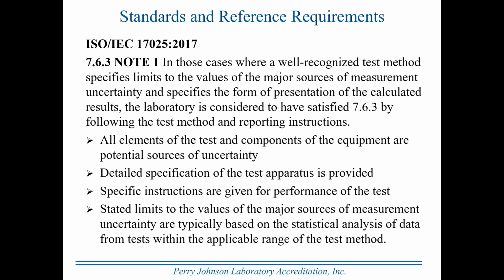Stated limits to the values of major sources or contributors of measurement uncertainty are typically based on the statistical analysis of data from tests within the applicable range of the test method. In other words, if the test method is good from some small magnitude to a large magnitude, then in the development of a published, internationally recognized test procedure, measurements or tests would be performed at the low end of the range, at the high end of the range, and various points between those. And that data would have statistical analysis applied, and from that would be test limits or acceptance criteria developed that would be used in determining suitability of the device or the material tested.